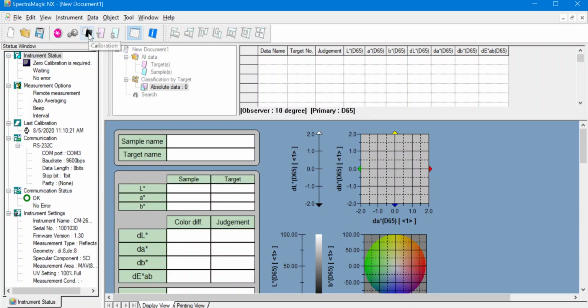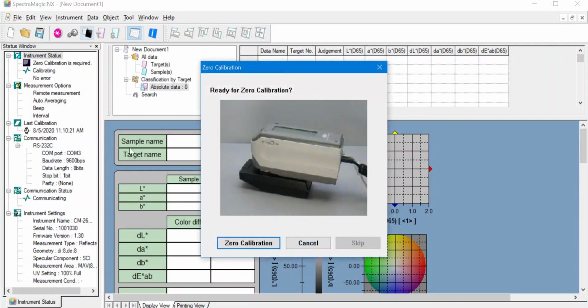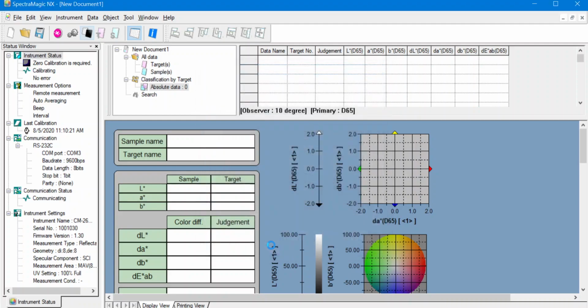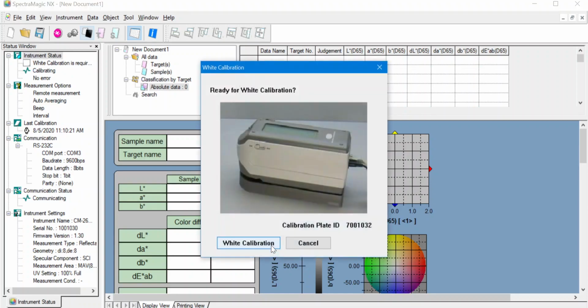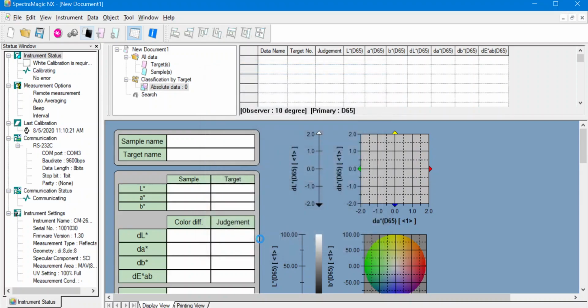So we click on this symbol, and there will be a small wizard that guides you. So it says ready for 0 calibration. So I will perform the 0 calibration. So I just have to click the word 0 calibration and set up the equipment accordingly for the 0 calibration. Okay. Now that it's done, it will prompt me for white calibration. So I will set up the equipment as shown in the image on the white calibration plate and click white calibration.